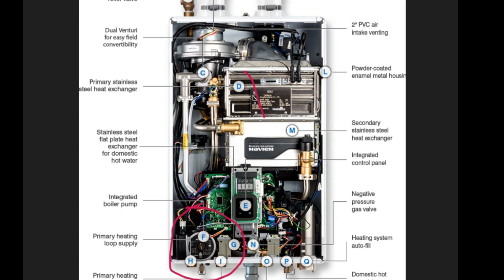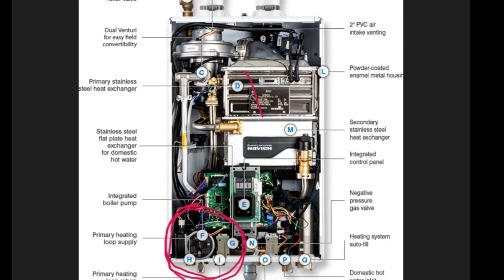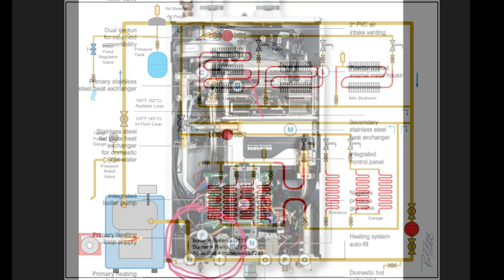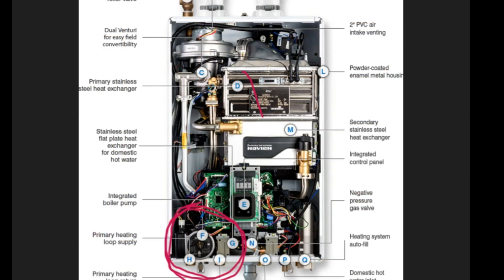So this pump is designed to regulate just the right amount of water through this heat exchanger to absorb heat at the proper rate. So even though five or six gallons per minute is the perfect flow rate through this heat exchanger to impart a lot of heat into that water, five or six gallons a minute moving through the entire piping system of the house and all the baseboard heaters just isn't enough in most cases to deliver enough heat to heat up the house.